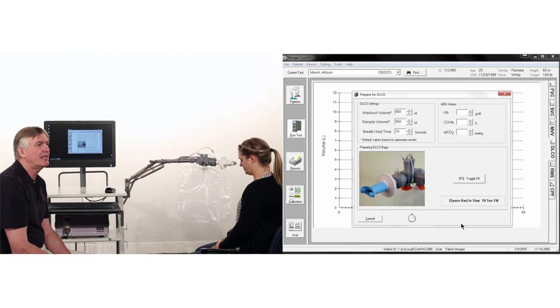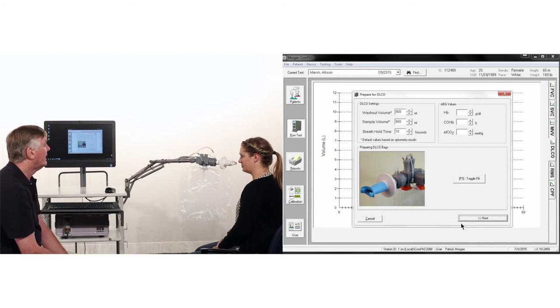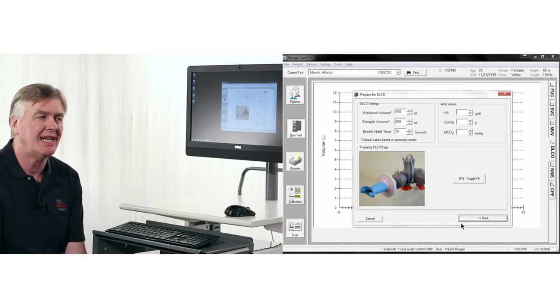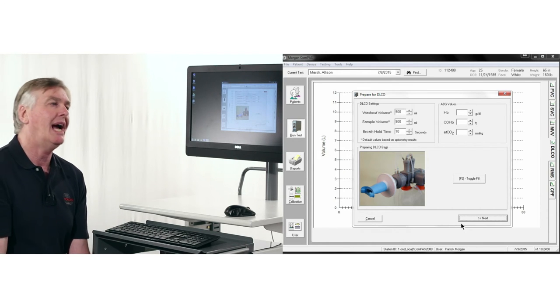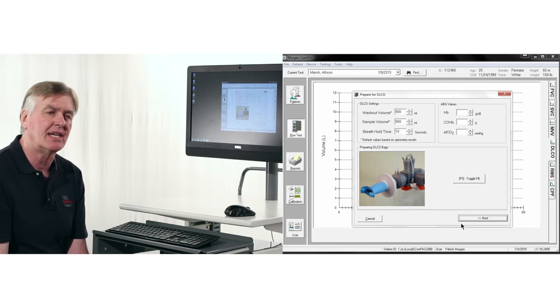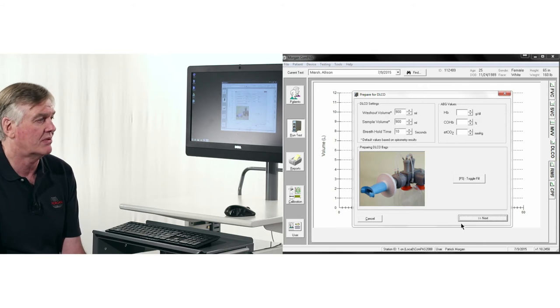A typical H cylinder will allow you to do 250 complete PFT studies, which might be two or three diffusions per study if necessary. At this stage, the bag is all set. It's ready at atmospheric pressure. So for the patient, it's extremely comfortable and normal to take a full breath in. We absolutely reject the use of demand valves in our products because it often causes a gag reflex and it's uncomfortable for the patient and can cause spurious diffusion results.